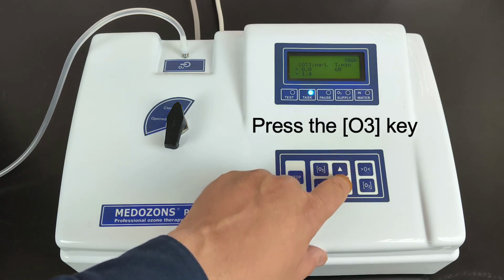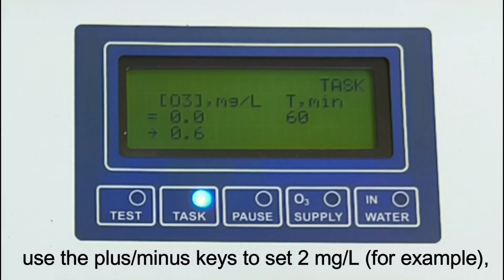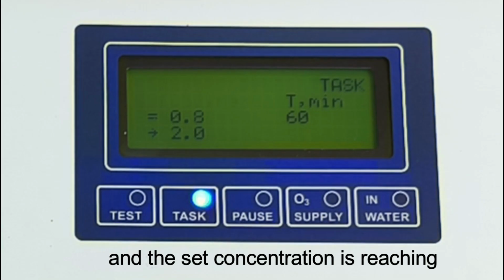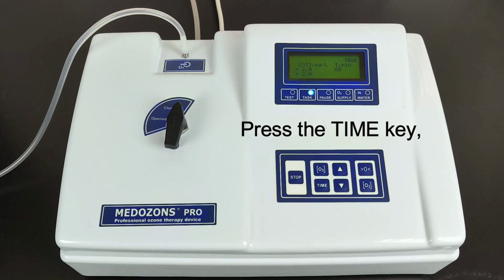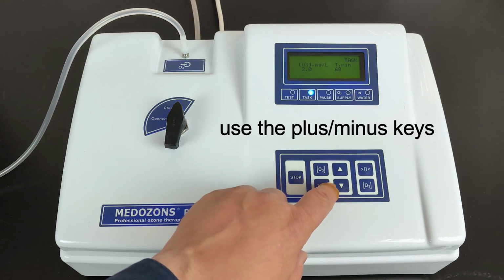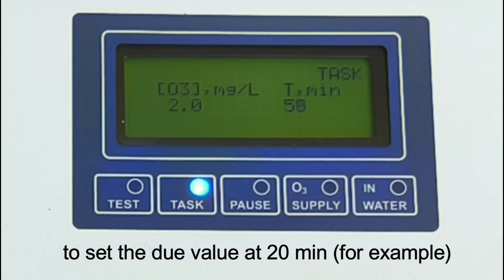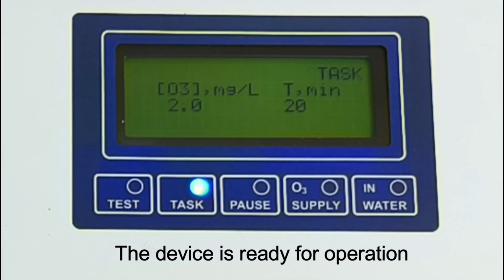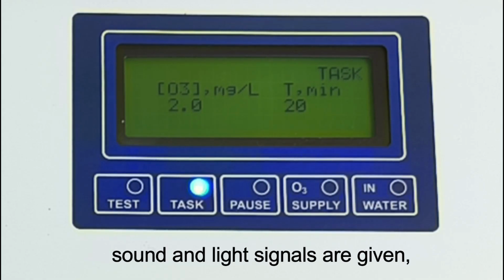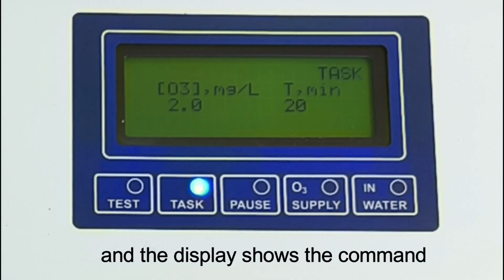Concentration. Press the O3 key, use the plus-minus keys to set 2 mg per liter, for example, and the set concentration is reached. Time. Press the time key, use the plus-minus keys to set the value at 20 minutes.